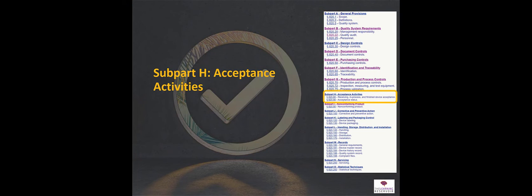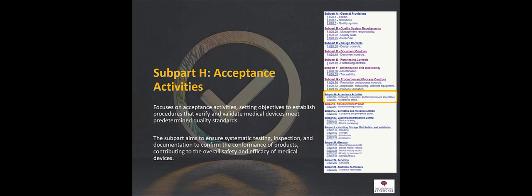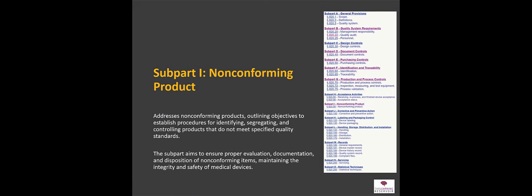Sub-part H is acceptance activities. How do we know when a medical device is acceptable, that it passes quality tests? What is the acceptable result and what is not? What in-process testing should be conducted? All of those things are covered under sub-part H.